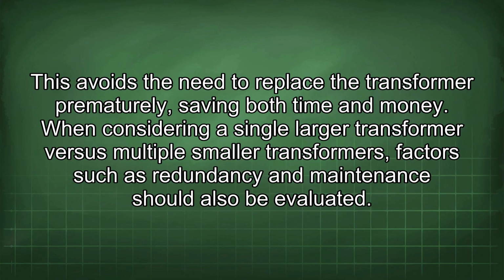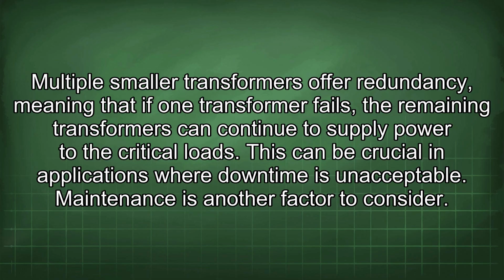This avoids the need to replace the transformer prematurely, saving both time and money. When considering a single larger transformer versus multiple smaller transformers, factors such as redundancy and maintenance should also be evaluated. Multiple smaller transformers offer redundancy, meaning that if one transformer fails, the remaining transformers can continue to supply power to the critical loads. This can be crucial in applications where downtime is unacceptable.